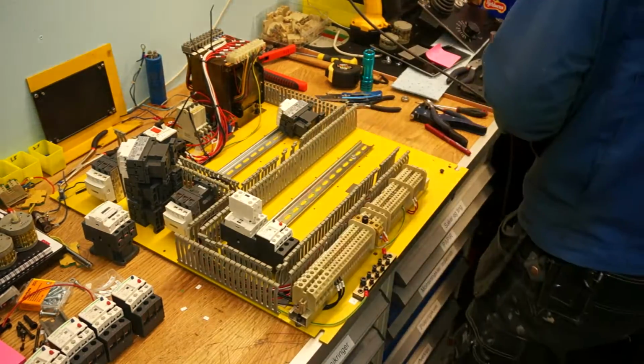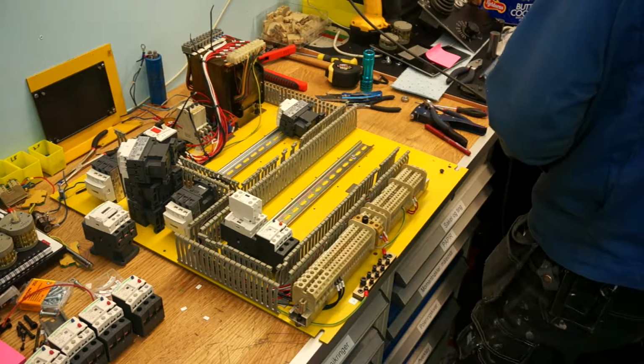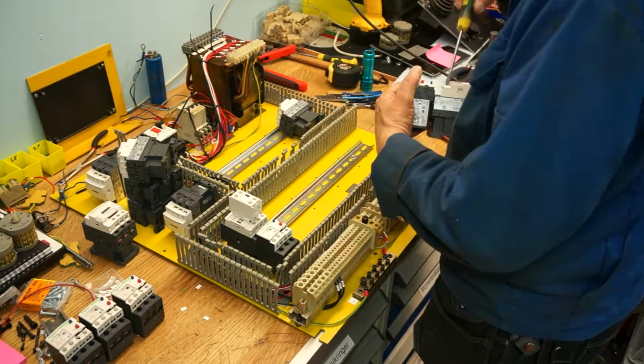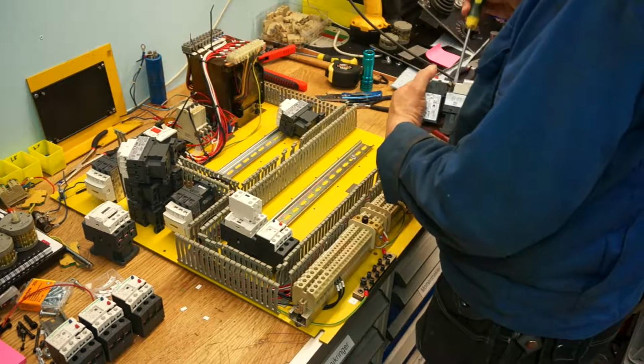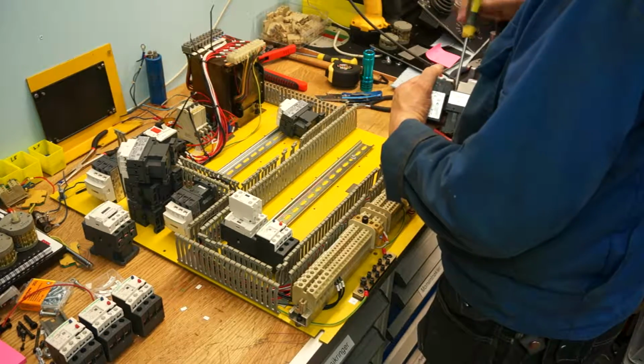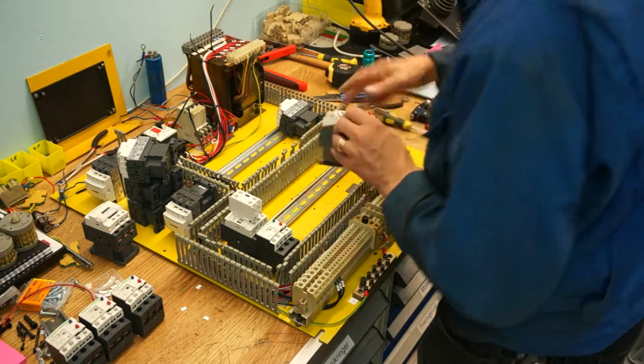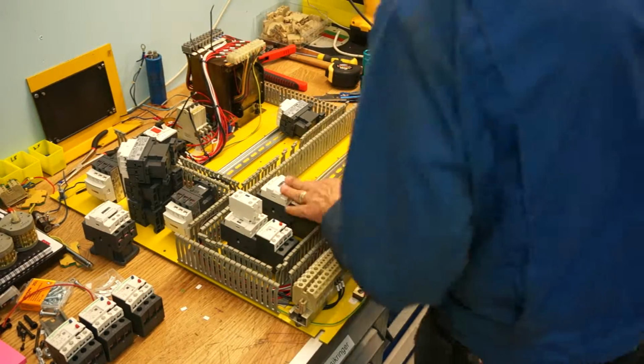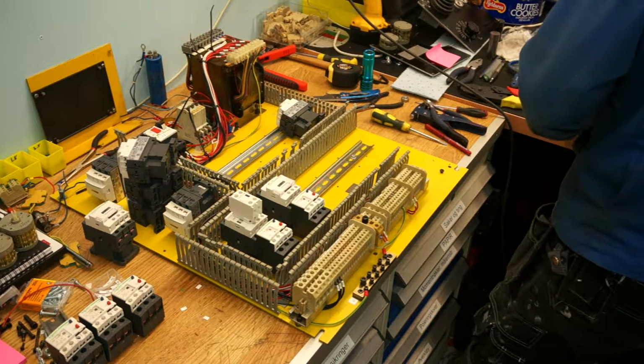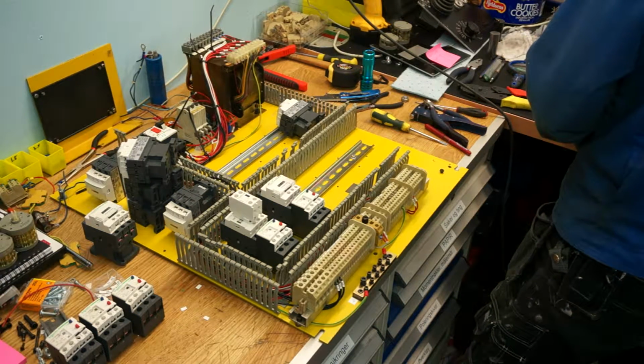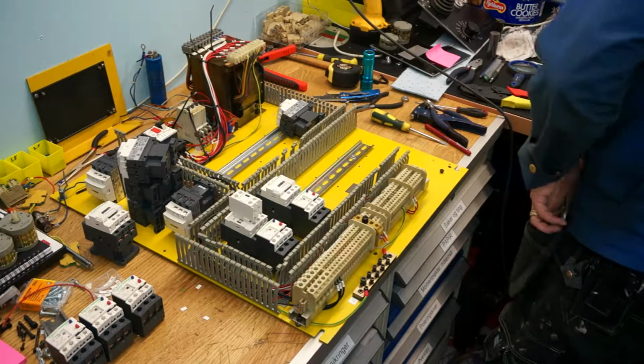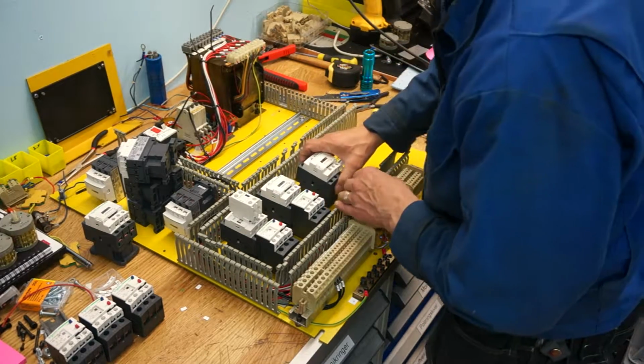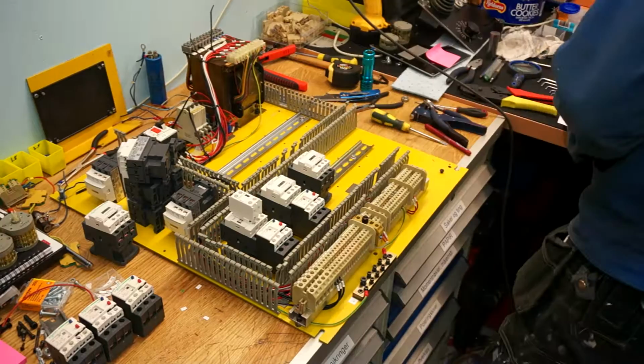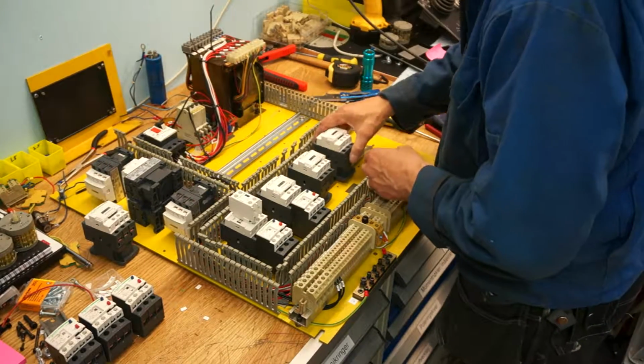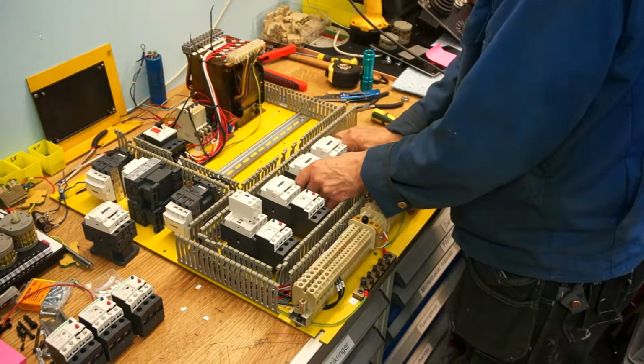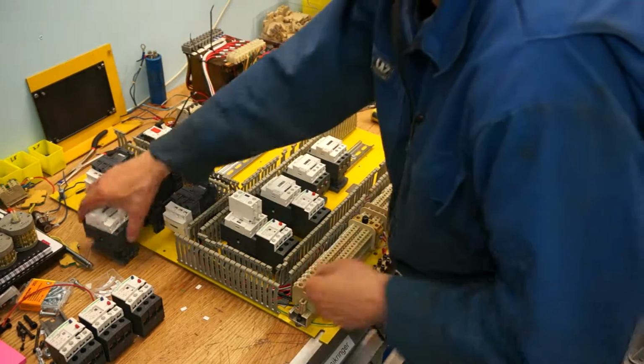On top of the contactor, there's some auxiliary switches, and there's also one or two on the contactor itself. These come in a variety of versions. The ones I have are one normally closed and one normally open, meaning one switch is closed and opens when the contactor is initiated, and the other one is the opposite - that's according to my needs in this project. Below the contactor is a thermal relay, which is like an add-on to a contactor. You can also get them as separate devices.